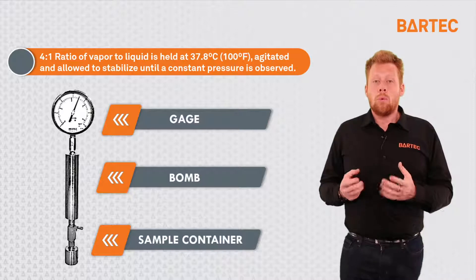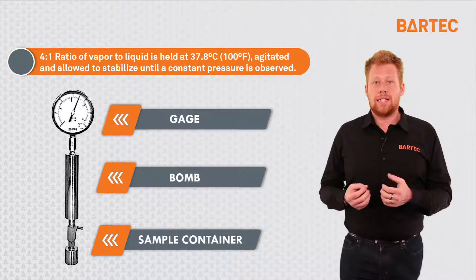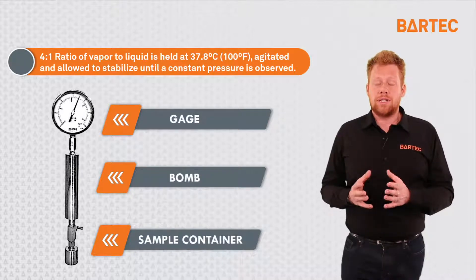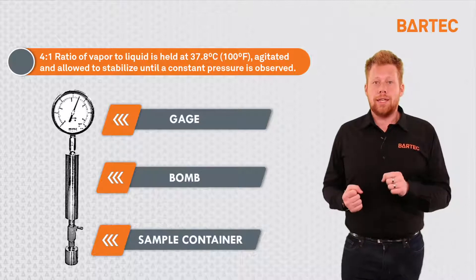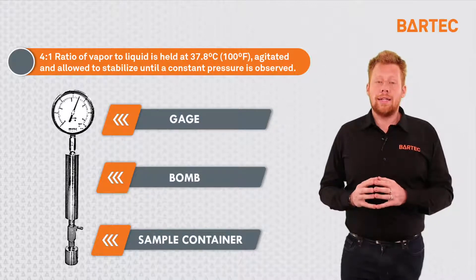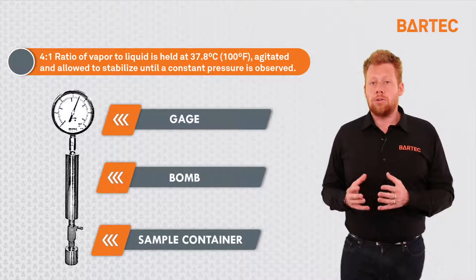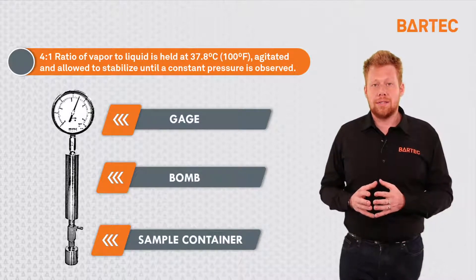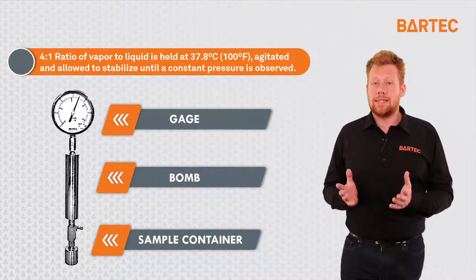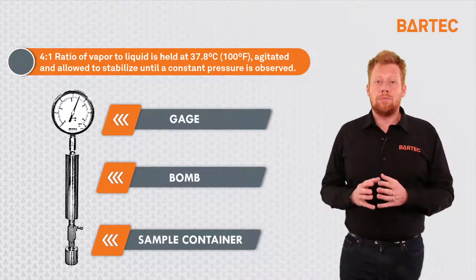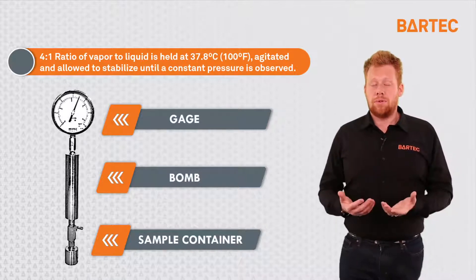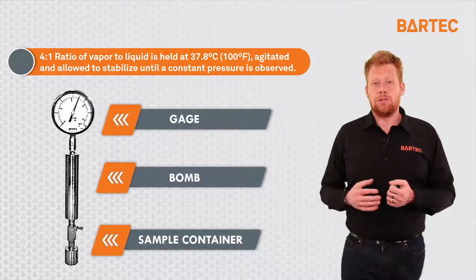Once the sample is exposed to the bomb where the vapors can get released, we will shake, agitate, and let the apparatus rest at a constant temperature of 100 degrees Fahrenheit or 37.8 degrees Celsius until the pressure gauge stabilizes. That stable pressure value is the vapor pressure of the sample at 100 degrees Fahrenheit.